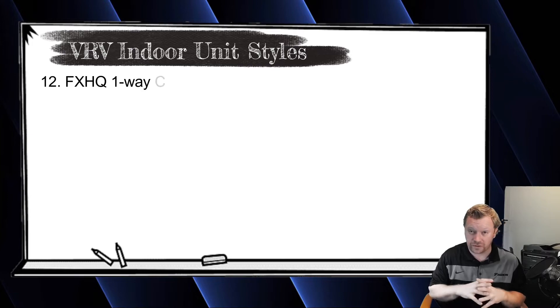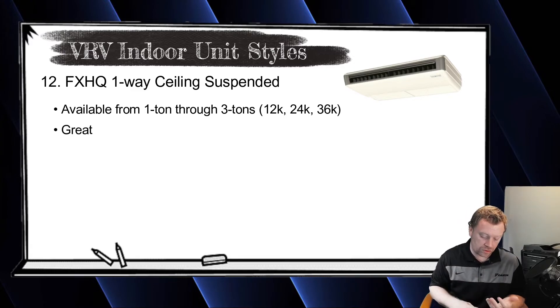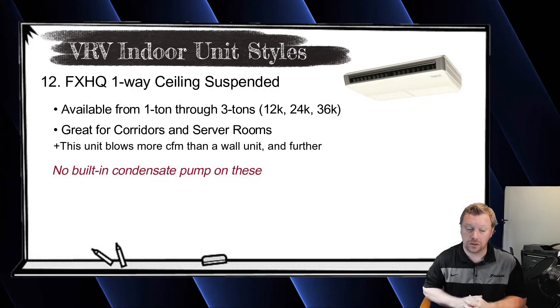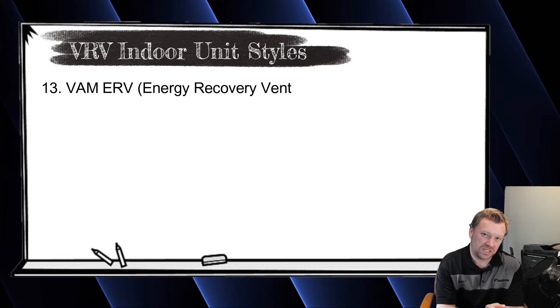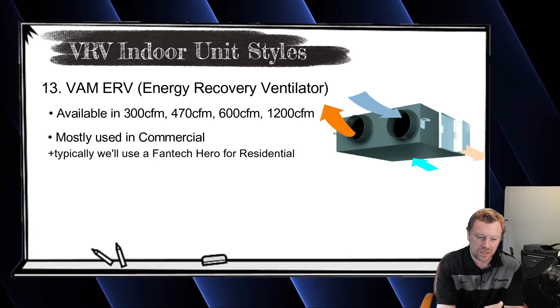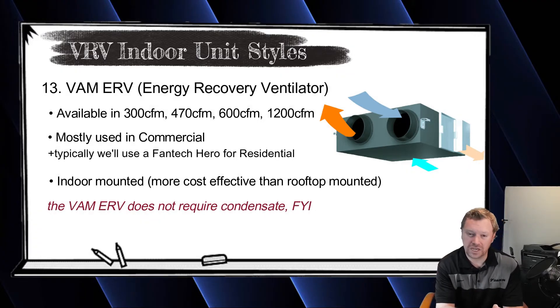The last unit is the FXHQ, another very old unit available in 1, 2, and 3 ton sizes. It's essentially a one-way throw ceiling-suspended unit — great for corridors where you need to throw air really far, and good for server rooms because wall mounts don't move as much air. The FXHQ units move a lot more air compared to wall mounts. There's also an ERV, though the smallest size is 300 CFM, which isn't always ideal for a home. For residential, the Fantech Hero is a good solution. For commercial, ERVs are available in 300, 470, 600, and 1,200 CFM flat horizontal units.